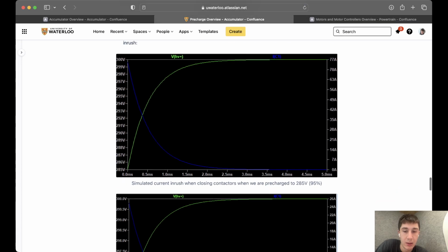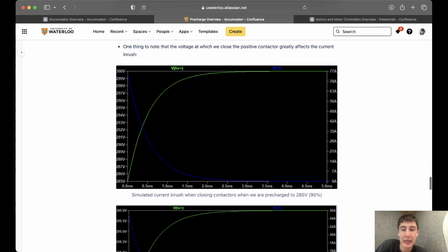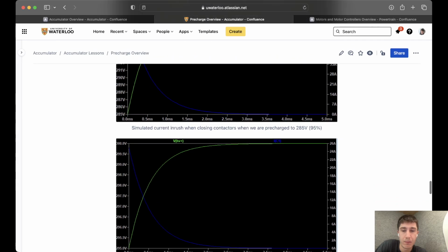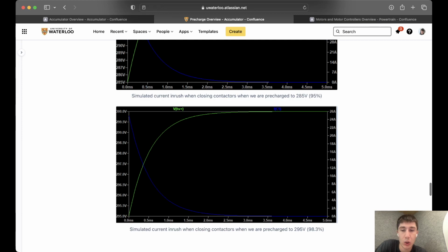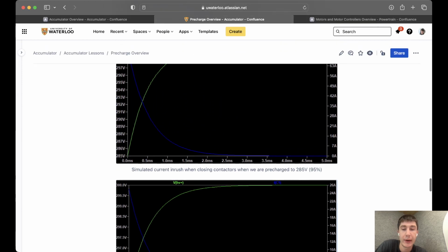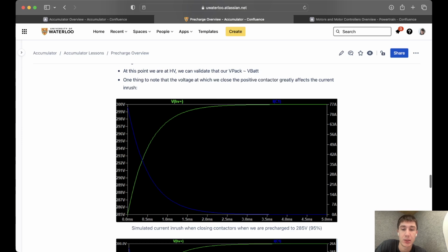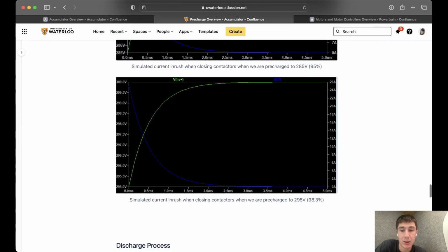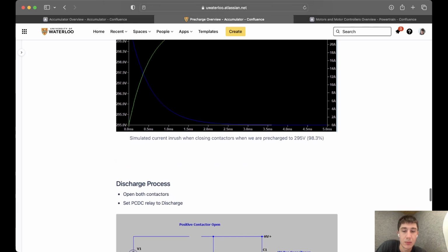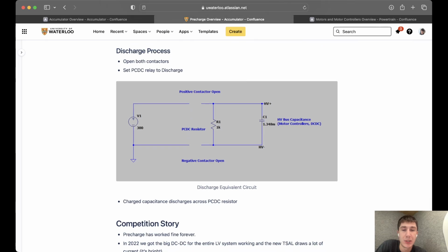So you can see here, when we close, if we start at 285 volts, we close the contactor, we actually get quite a large spike in current. But as we close at higher bus voltages, at 285 volts, we get 70 amps of inrush current, quite a bit. At 295 volts, we get 26 amps, which is also quite a bit, but it's for a very, very small time scale, as you can see. It decays to 0 amps in 4 milliseconds. And that is our precharge process.